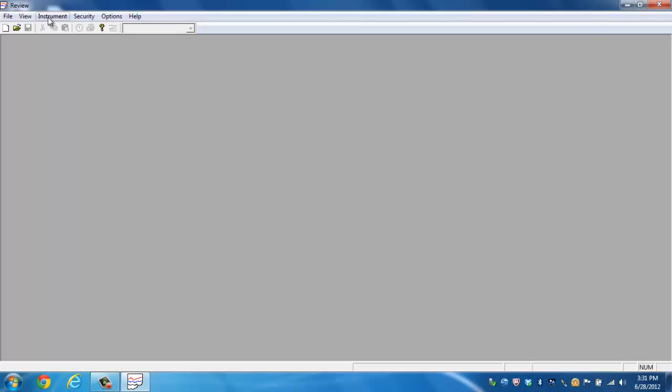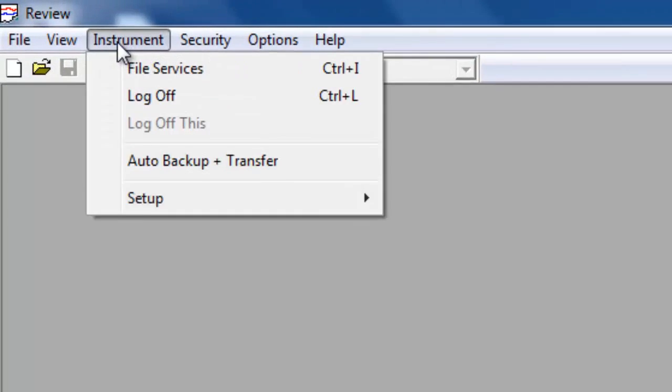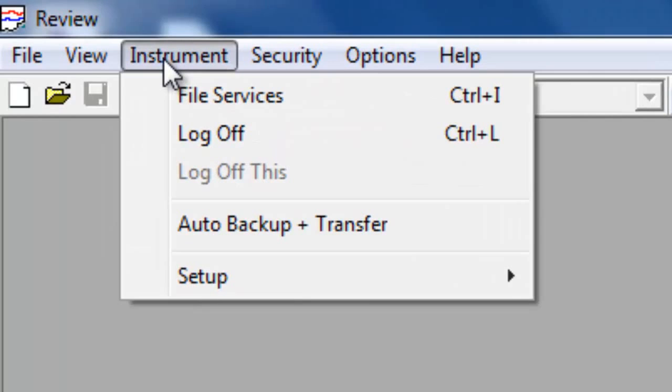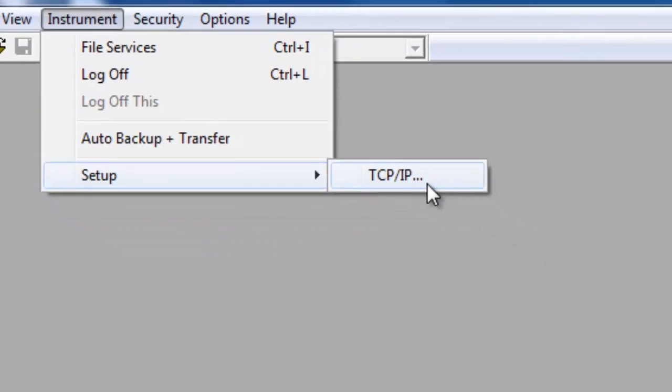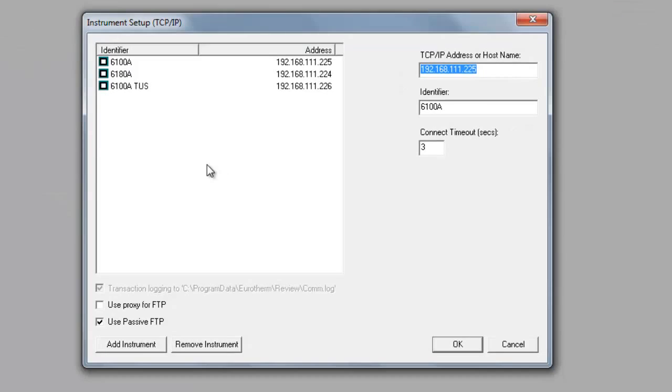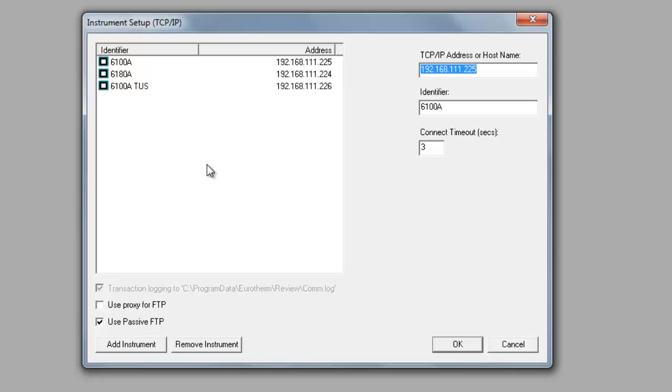If you're doing something over the network, this involves one other simple step. Underneath the instrument tab there is an option at the very bottom underneath setup called TCP IP. Within this window, this is where you can add all your individual instruments. So in the event that you've got multiple recorders in your facility, you can plug them into this configuration with their individual IPs and have Review go out to all your recorders and pull all that data into the review.